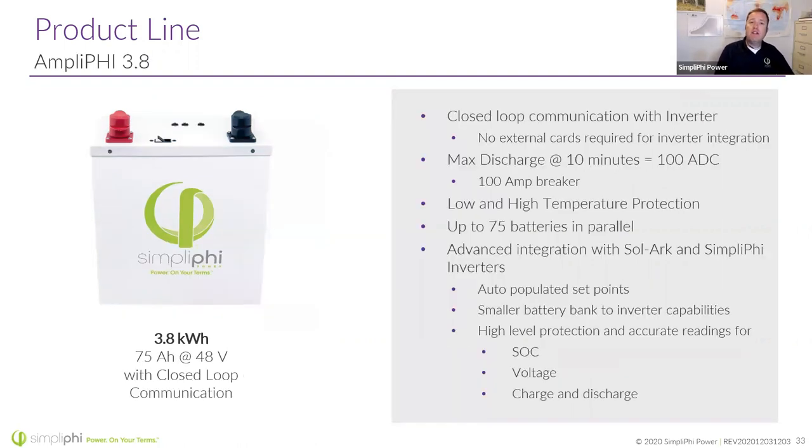Here's the AmpliPHI — the one that does have closed-loop communication capabilities. It also has a slightly higher max discharge rate. The best part about closed-loop communication is that it auto-populates set points in inverters and gives a very accurate state-of-charge reading. So it's not like the old off-grid days where the homeowner is walking out to the power shack and looking at the voltage of the batteries. Homeowners want an app with a fuel gauge to know exactly where their batteries are at, and having closed-loop communications helps deliver that accurate fuel gauge.